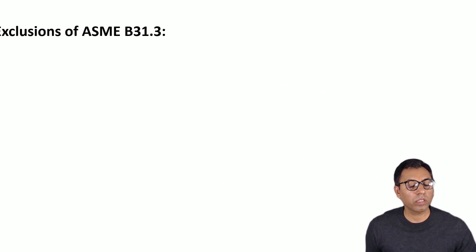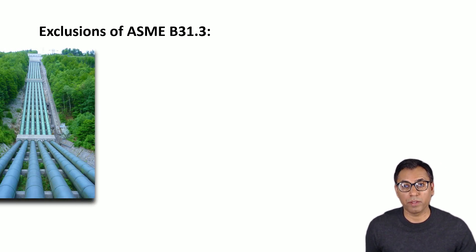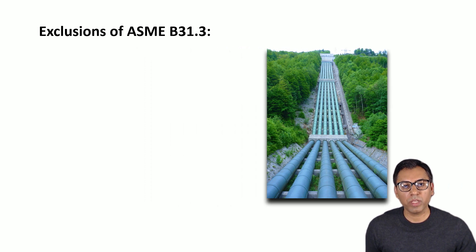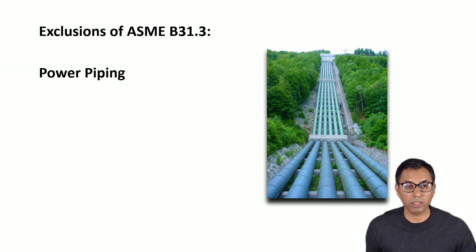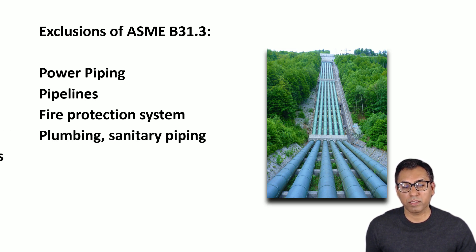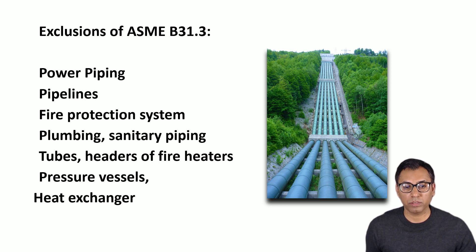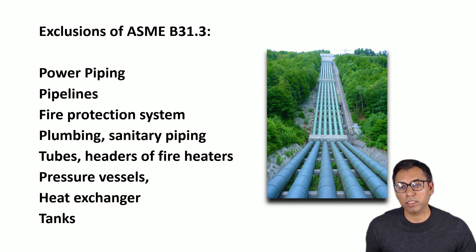Now let's talk about the exclusions — where ASME B31.3 piping code does not apply. In the following cases, B31.3 is excluded: piping used in power and boiler systems, pipelines, fire protection systems, plumbing and sanitary piping, tubes and tube headers of fired heaters, pressure vessels, heat exchangers, and tanks. In these categories, B31.3 does not apply.